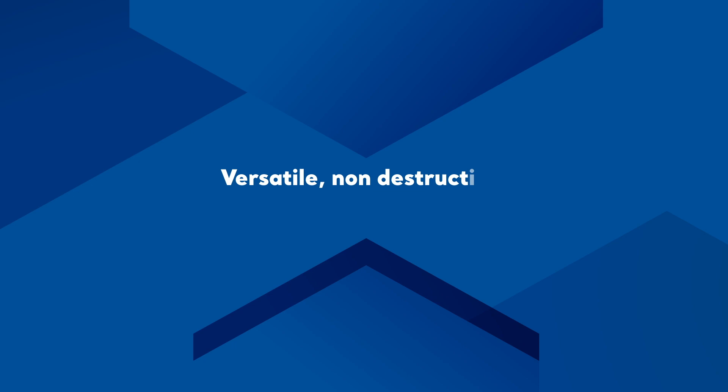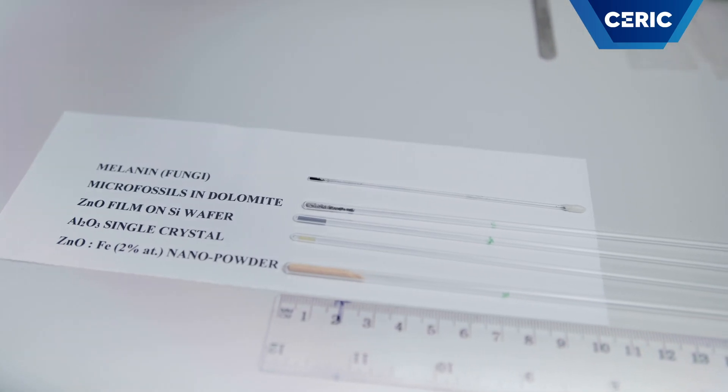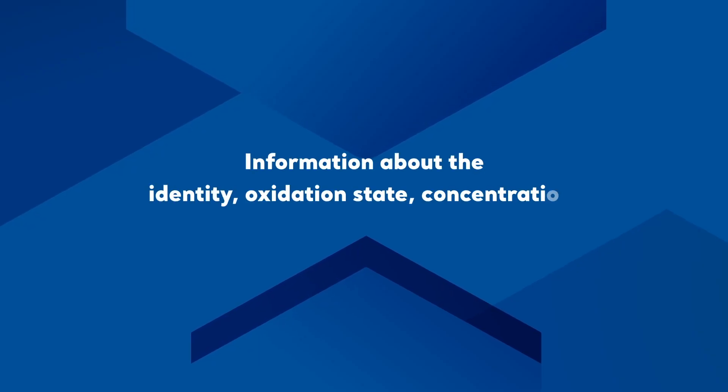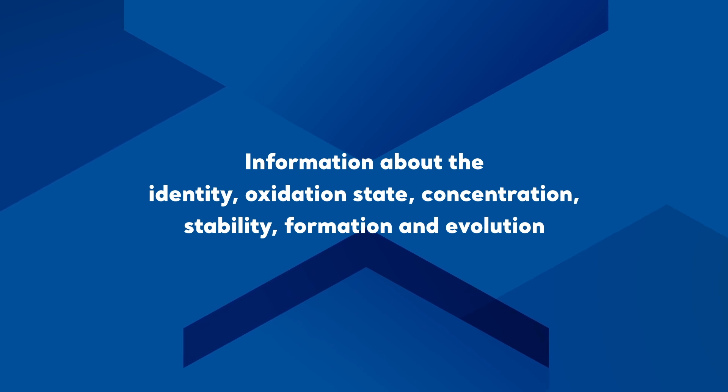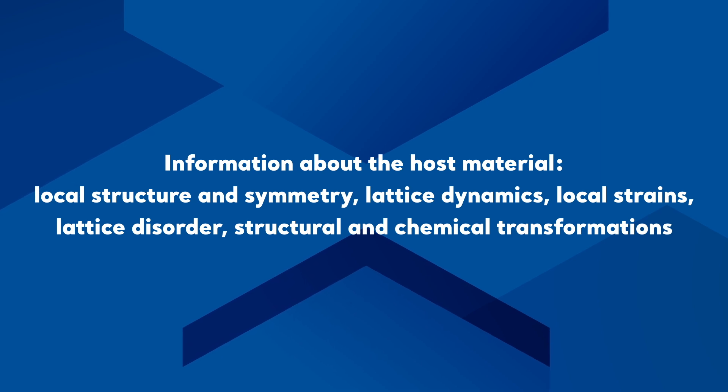EPR is a versatile, non-destructive, highly sensitive analytical method. It can detect concentrations of paramagnetic species as low as 10 to minus 4 percent. The samples can be in powder form, single crystals or films cut to sizes compatible with the quartz EPR tubes. However, the film substrate should have higher electrical resistivity and a very low content of paramagnetic impurities. The EPR characterization of the paramagnetic species involves the determination of their identity, oxidation state, concentration, stability, formation and evolution. Some species are also used as paramagnetic probes to obtain information about the host material, such as local structure and symmetry, lattice dynamics, the presence of local strains, and the degree of lattice disorder.